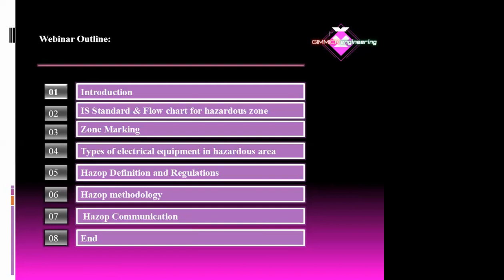And the next one, IP, ingress protection. IP means ingress protection. It is two numbers in numerical form. The first value discusses protection against powder. The second value talks about protection against water, in the form of jets, immersion, mist, or spray. The maximum protection is 68: 6 is the maximum for powder and 8 is the maximum for water. So if you have a 68 type motor, it is safer.